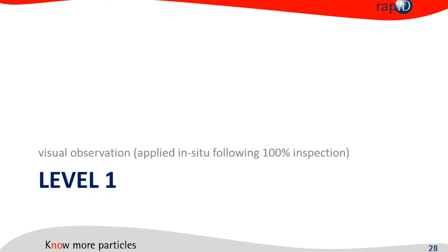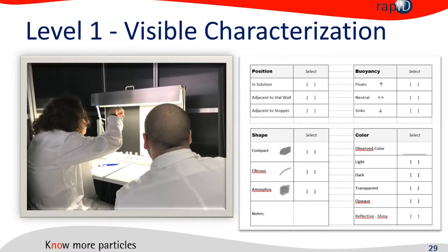Level one is visual observation — it's very important not to confuse this with visual inspection. This comes after the 100% visual inspection that's already done, using similar tools. In training, attendees use a worksheet: they observe if the particle is floating in solution, then swirl it and observe buoyancy — does it go up, is it neutral, does it sink?